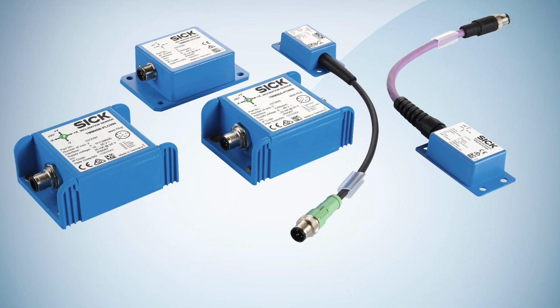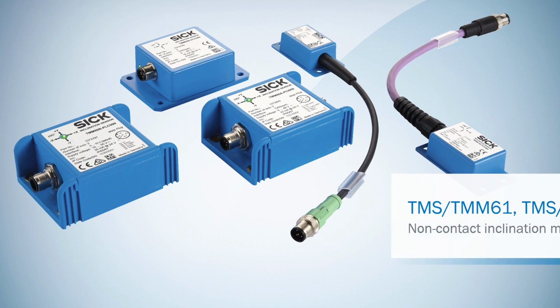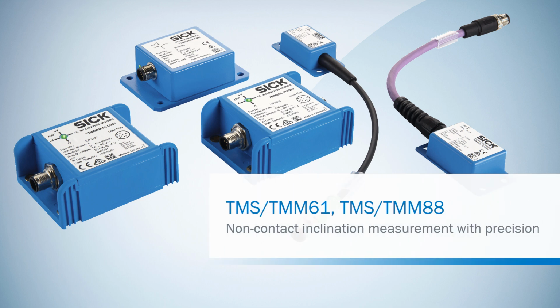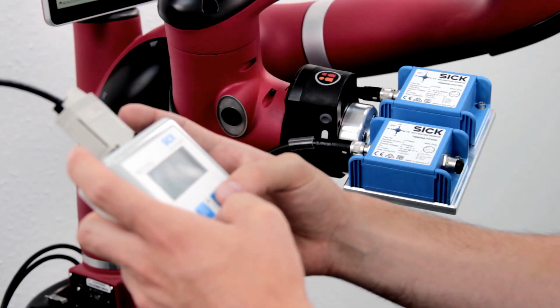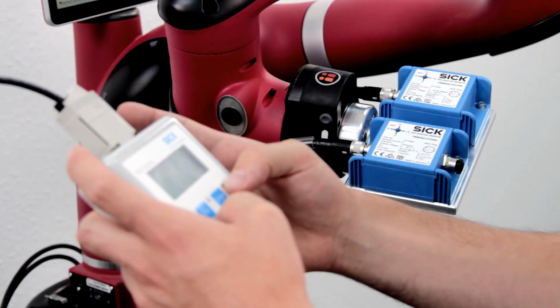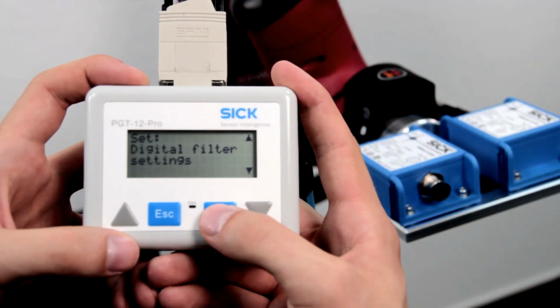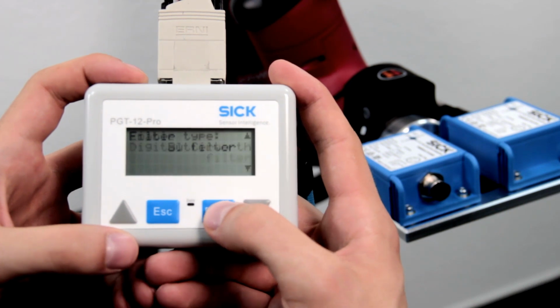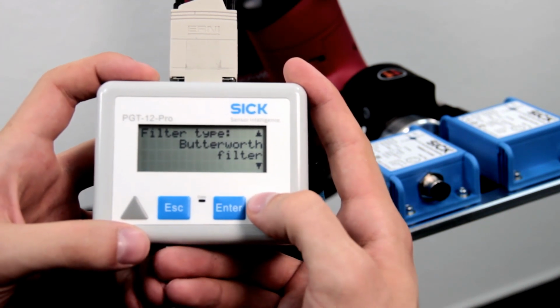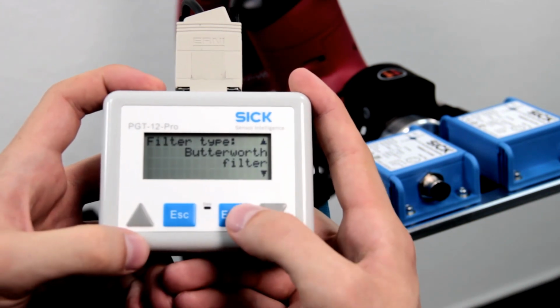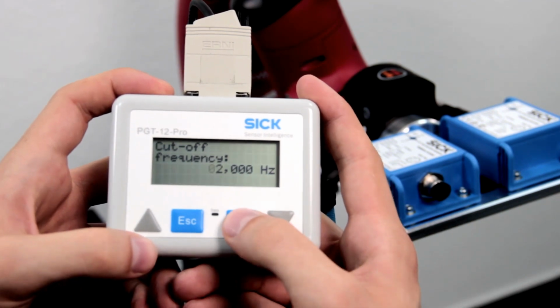In this video, we will demonstrate how to adjust the filter settings on an inclination sensor from SICK to obtain optimum signals. Different filter settings allow compensation of unwanted vibrations and oscillations from the signal. You can choose between two different filter types, the so-called Butterworth filter and the critically damped filter. Each filter type offers different advantages for your application.